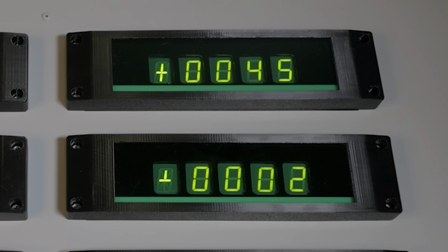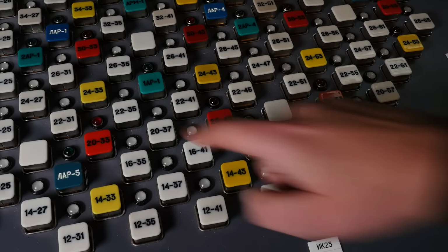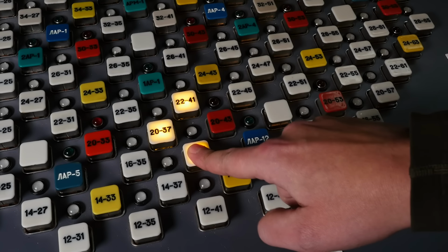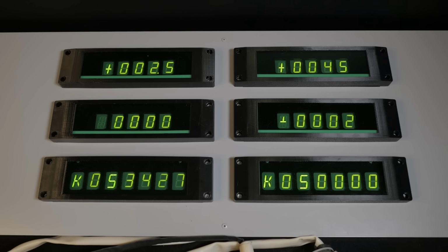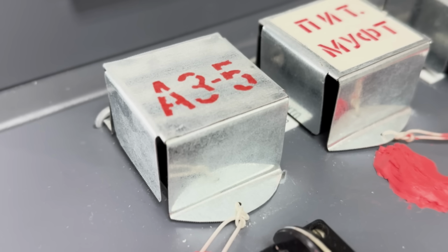It's basically a special number that tells the operator how controllable the reactor is. SKALA calculates the combined effect of all the control rods currently inside the core, and then it expresses it as an equivalent number of fully inserted manual control rods. A normal value is approximately 45 to 48 rods. If the number falls, it means that more rods have been withdrawn and the reactor has less control reserve remaining. So the warning set point is 43 rods, and if the margin falls to 30 rods, continued operation is no longer permitted. In this case, the reactor must be shut down.